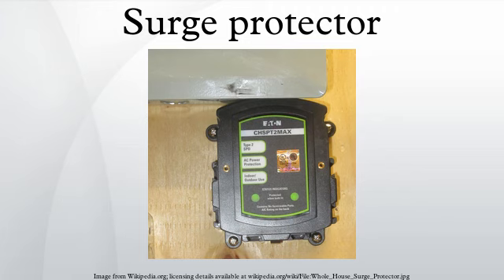Due to their exceptionally low capacitance, GDTs are commonly used on high-frequency lines, such as are used in telecommunications equipment. Because of their high current handling capability, GDTs can also be used to protect power lines, but the follow-on current problem must be controlled. Selenium voltage suppressor, an overvoltage clamping bulk semiconductor similar to an MOV, though it does not clamp as well. However, it usually has a longer life than an MOV. It is used mostly in high-energy DC circuits, like the exciter field of an alternator.